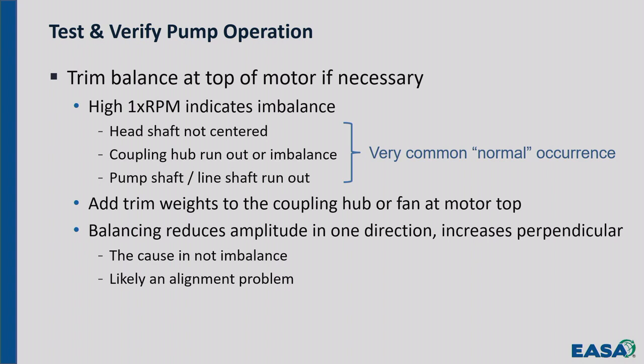You've got a head shaft that goes through the hollow shaft, through the pump shaft. There's no guarantee it's in the middle. That's a rifle-bored motor shaft, and that bore is not 100% true. The pump shaft can be off to one side or another, throwing it off a little bit and creating some imbalance. You could have coupling issues, okay? Coupling hub runout, either on the top or on the bottom. On the top if it's a hollow shaft, on the bottom if it's a solid shaft. Or you could have issues with the pump shaft.